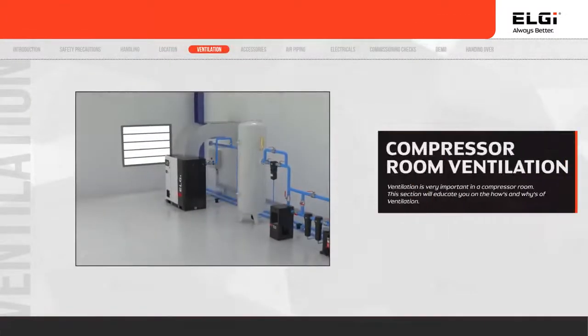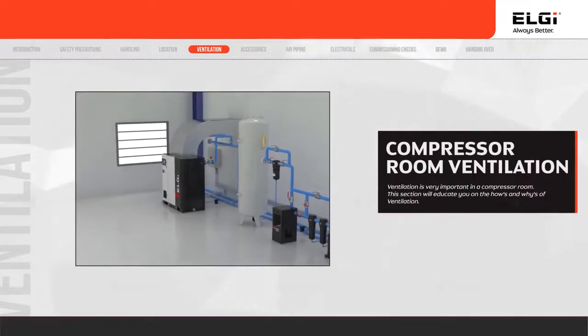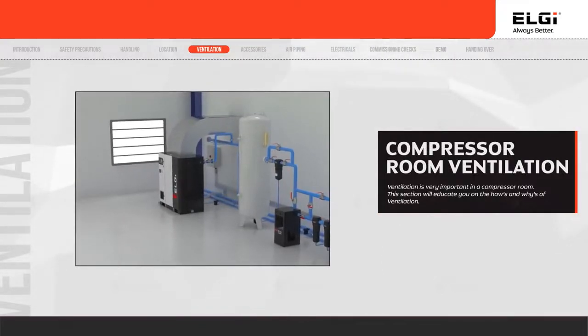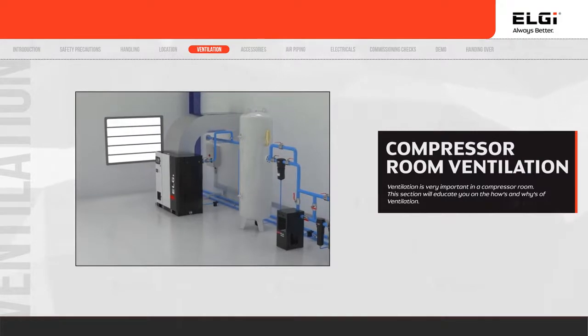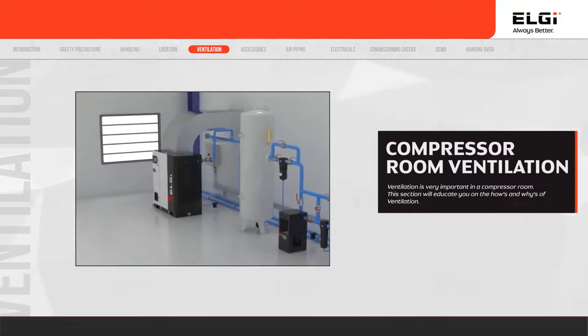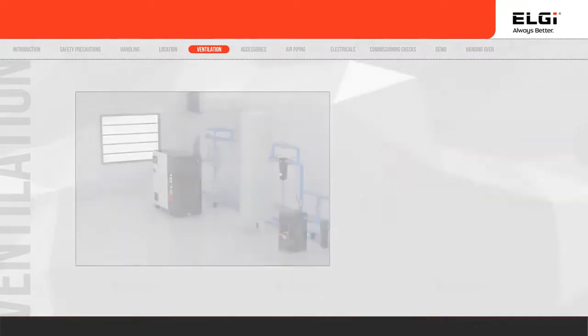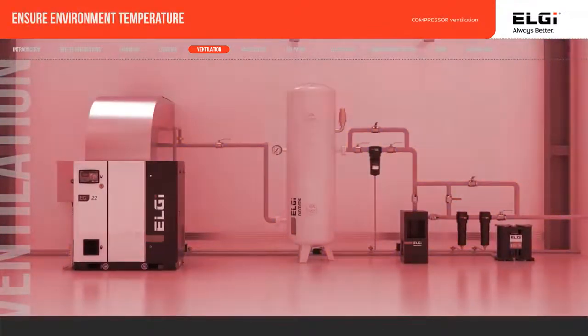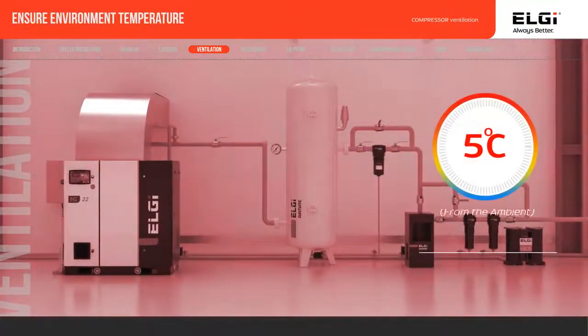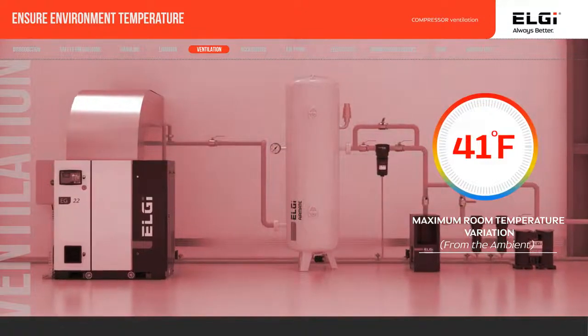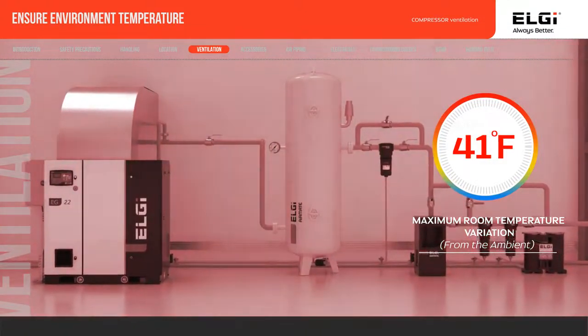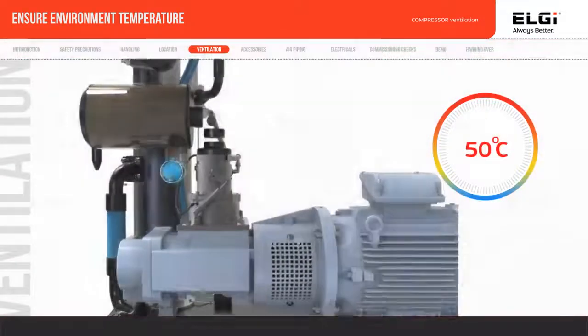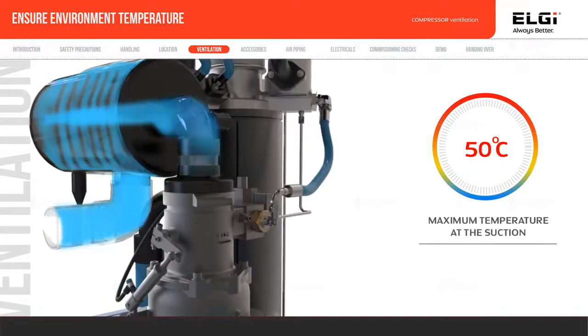Proper ventilation is very important for a compressor to function efficiently. Let's understand various aspects related to ventilation while installing an Elgi compressor. The compressor room temperature should not be more than 5 degrees Celsius, 41 degrees Fahrenheit, from ambient. Ensure the compressor suction temperature is within 50 degrees Celsius, 122 degrees Fahrenheit.